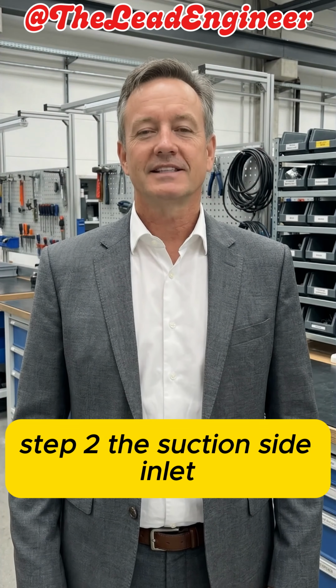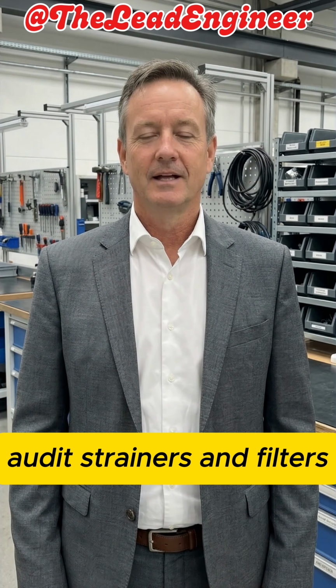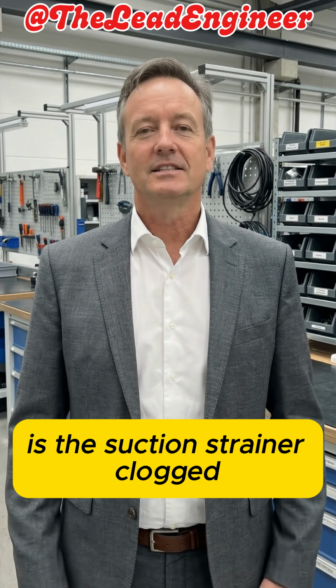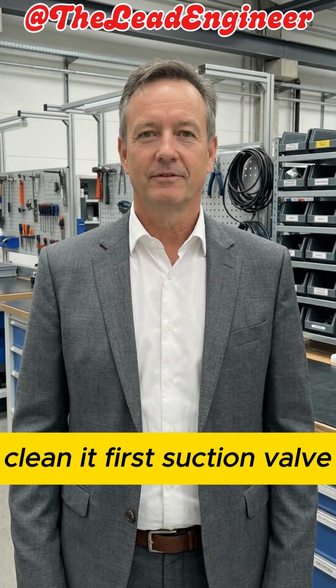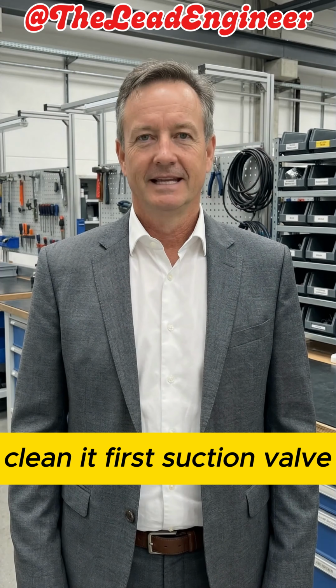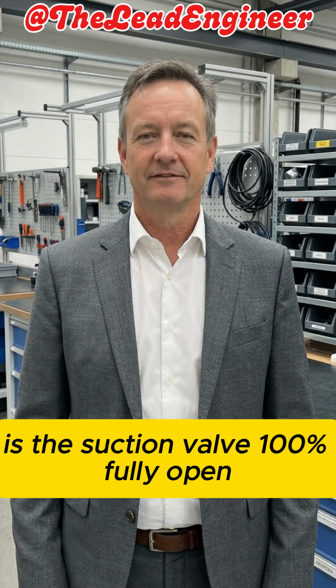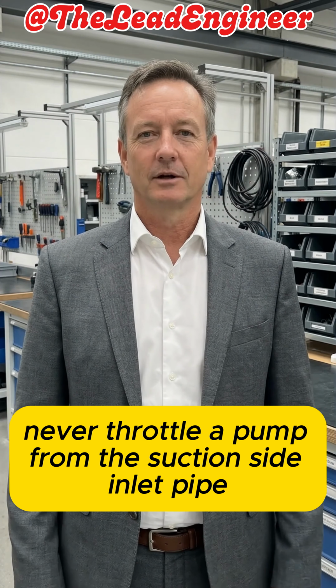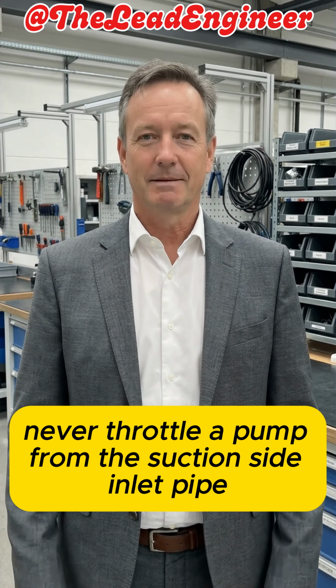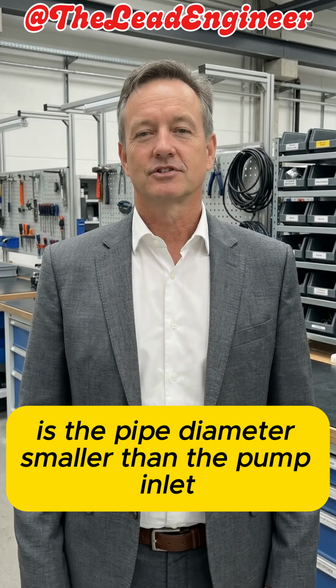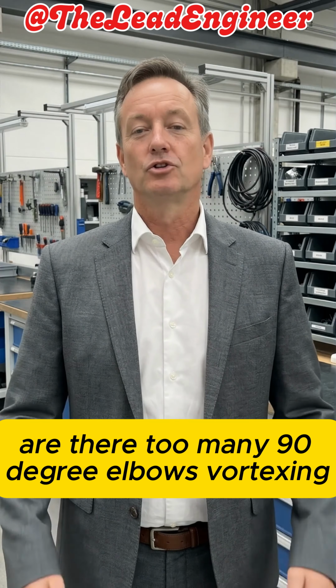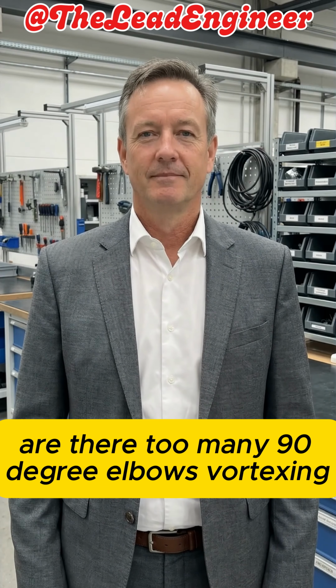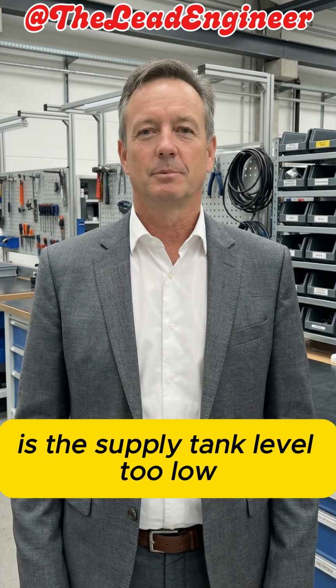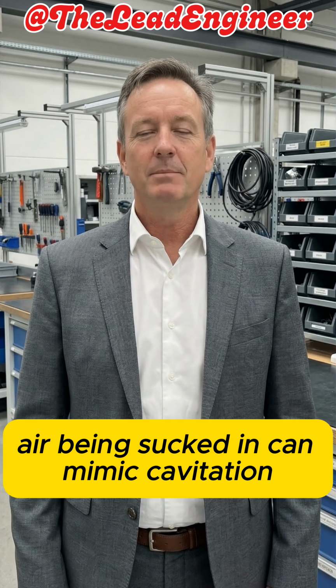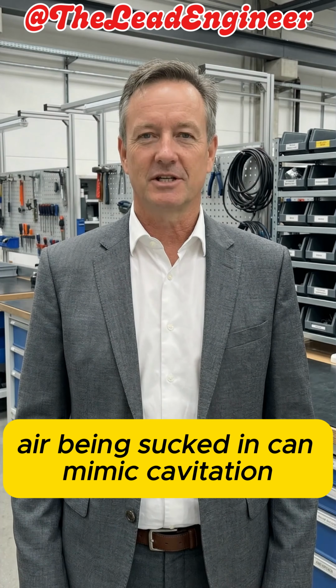Step 2. The suction side inlet audit. Strainers and filters. Is the suction strainer clogged? Clean it first. Suction valve. Is the suction valve 100% fully open? Never throttle a pump from the suction side. Inlet pipe. Is the pipe diameter smaller than the pump inlet? Are there too many 90-degree elbows? Vortexing. Is the supply tank level too low? Air being sucked in can mimic cavitation.